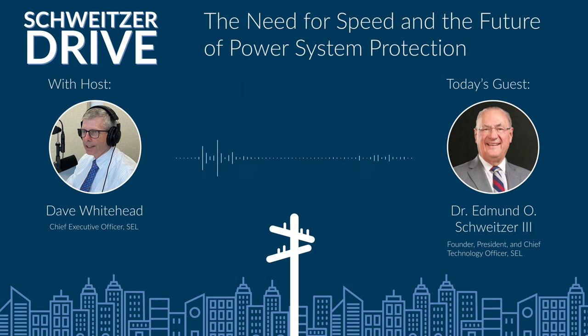That's right, Dave. If the pre-fault load current is 100 amps and there's a fault on that line, the traveling current wave that gets launched is going to be something like the voltage of the line divided by the surge impedance. So it might be a few hundred amps. That's hardly anything compared to the 5 or 10 or more thousands of amps that are going to flow when those sources finally dig in, sometime later, in another 4, 8, 10 milliseconds. And meanwhile, back at the ranch, we're done. We're done and out of there in 1 or 2 milliseconds today. And you're right. We can really beat the clock when it comes to telling the breaker to get going when there isn't much current out there. Pretty cool, isn't it? It's really cool.